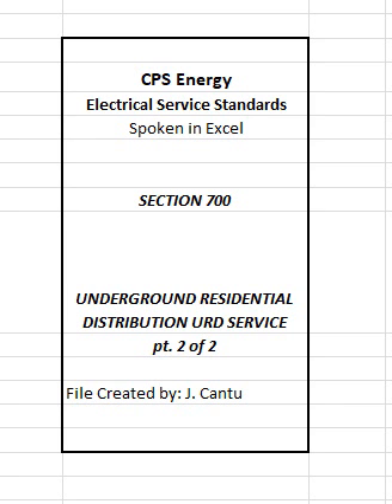704 Clearance from other buried utilities. Clearance of service conduits from other buried utilities shall be 12 inches minimum for commercial service installations, and for residential service installations random lay will be permissible. Depth of trench shall be coordinated with CPS Energy's customer service representative to assure minimum clearances are maintained.